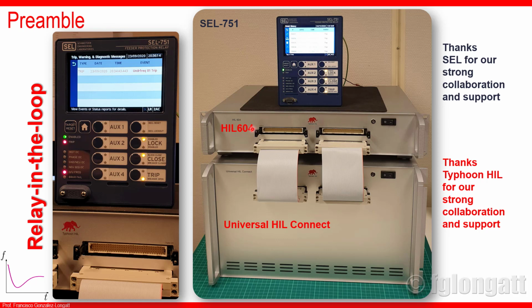Inside this Typhoon-HIL 604 real-time simulator, I had a power system creating the under frequency event. Then, using the digital and analog inputs and outputs, I sent signals to this big element, the HIL Connect, in order to condition the signals for this relay.